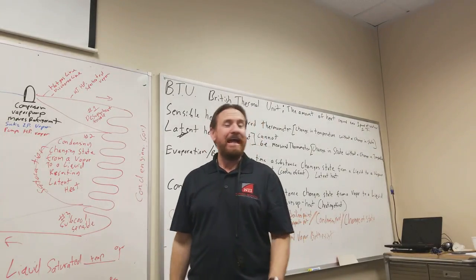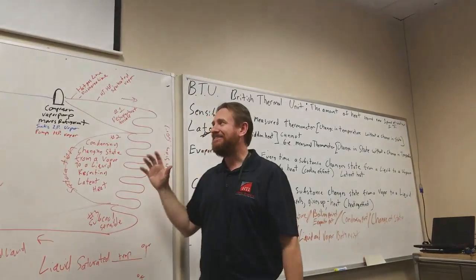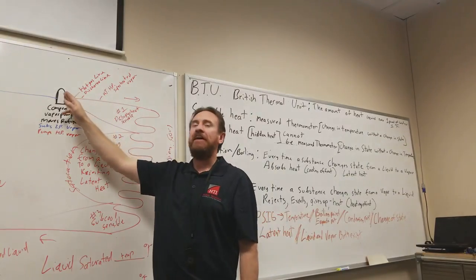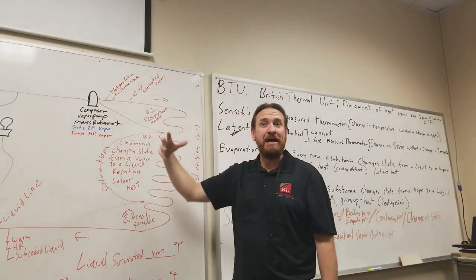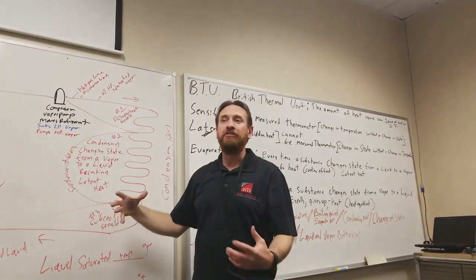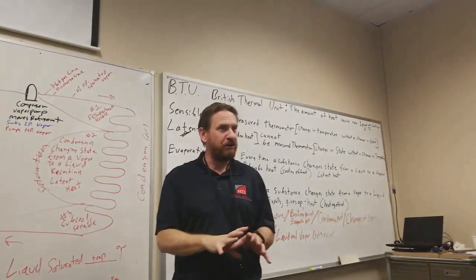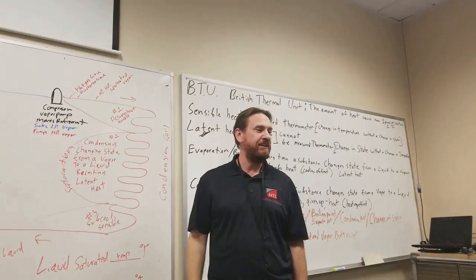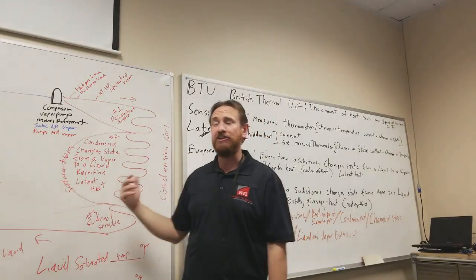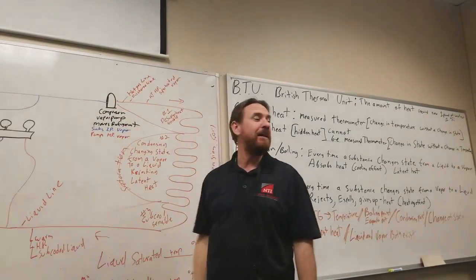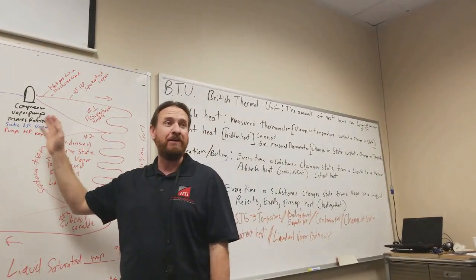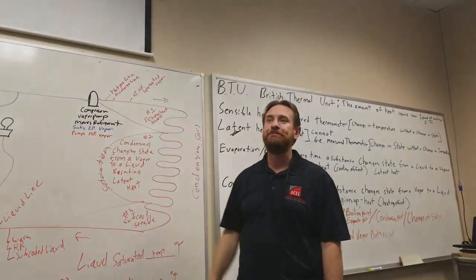And as it gets hotter, that's a good point. As it gets hotter, the pressure goes up even more, and it affects the compression ratio. The pressure ends up having more work going on. There is more back pressure pushing against the motor, but it still turns at the same speed. It just is going to use more electricity. The compression ratio is going to change. A lot of stuff's going to change, but the motor can't speed up. It can't go faster. The ones we're talking about don't change. They're the same speed all the time.